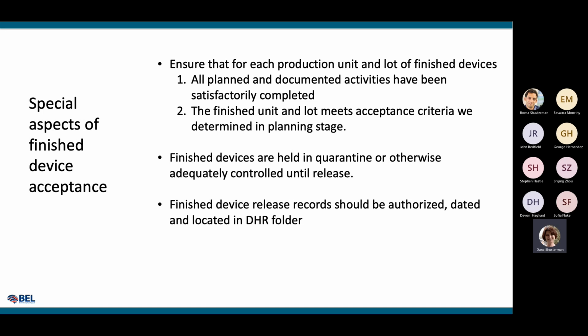Finished devices should be held in the quarantine area until released. And finished device release records are authorized, dated, and located in the DHR folder.